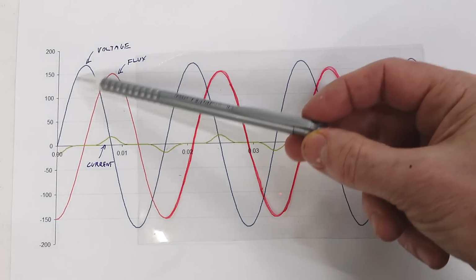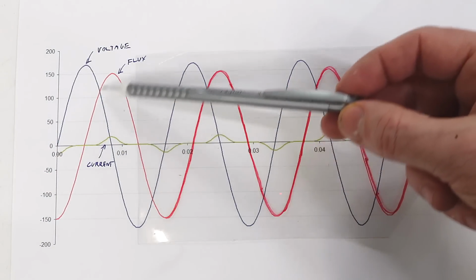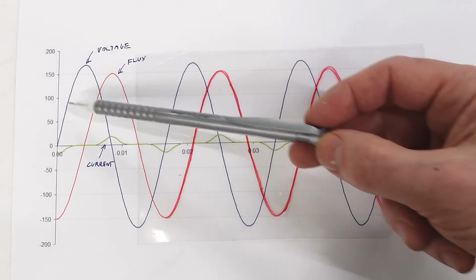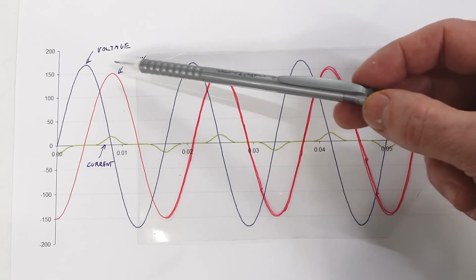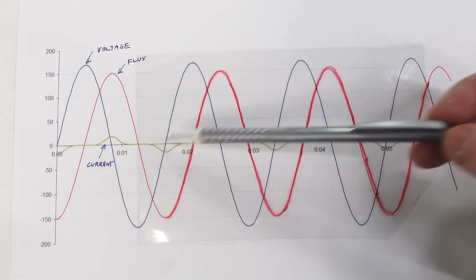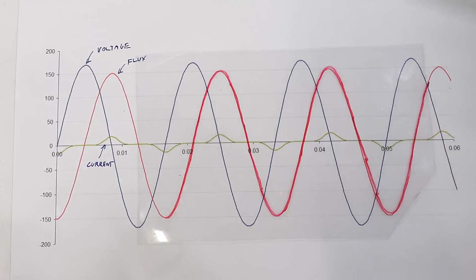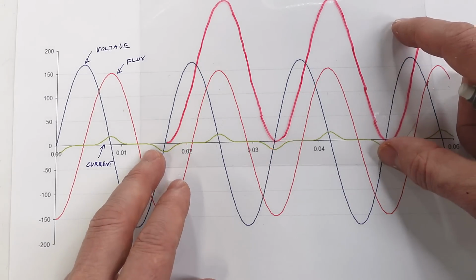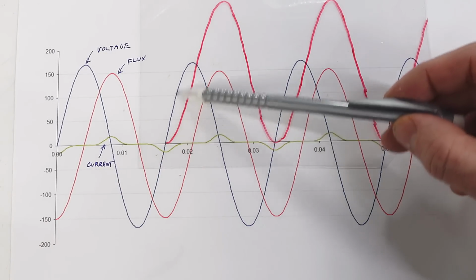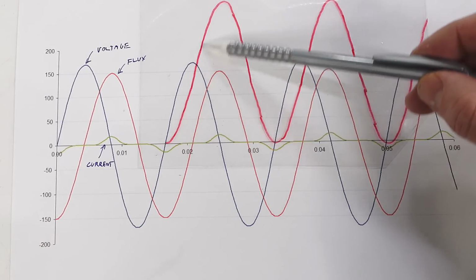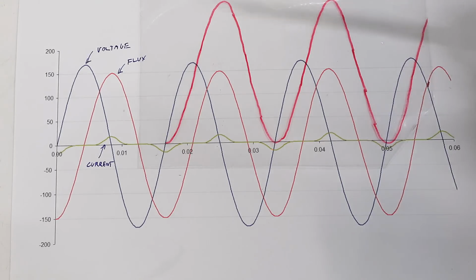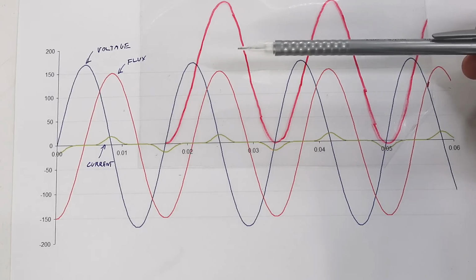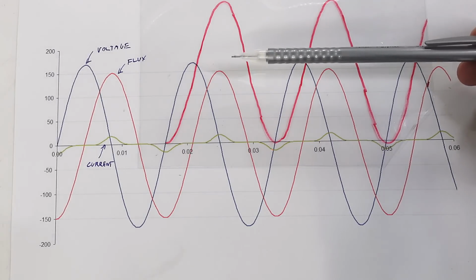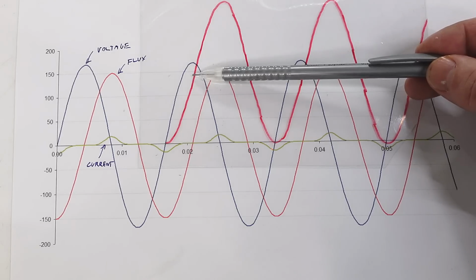The induced voltage in a transformer is a function of the rate of change of flux, but if you're controlling the voltage, the flux ends up being essentially the integral of the voltage. When the voltage is at the zero crossings, the flux is always at its maximum. But if we turn the transformer on right when the voltage is at a zero crossing, it starts with zero flux, and as we integrate over this part of the curve, the flux goes way up. The problem is the core usually runs very close to saturation, since that makes for a smaller transformer, so we're already starting to run into saturation right about here.